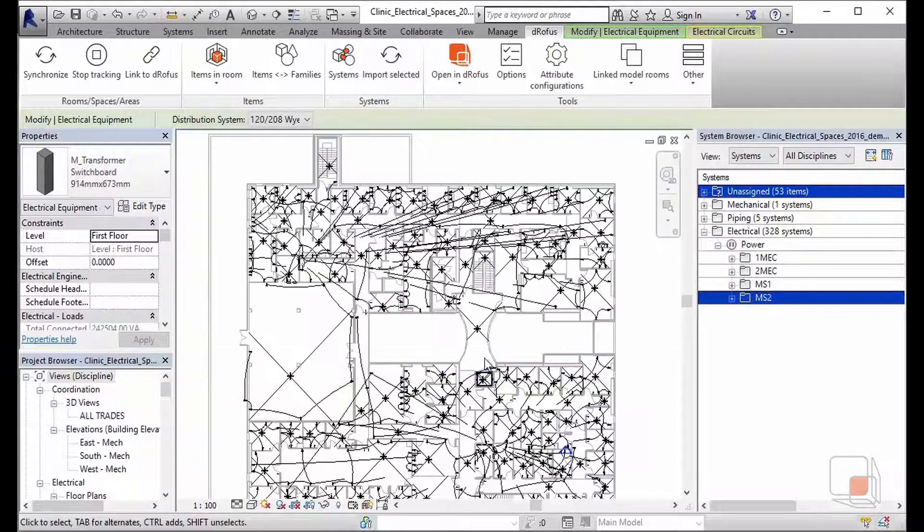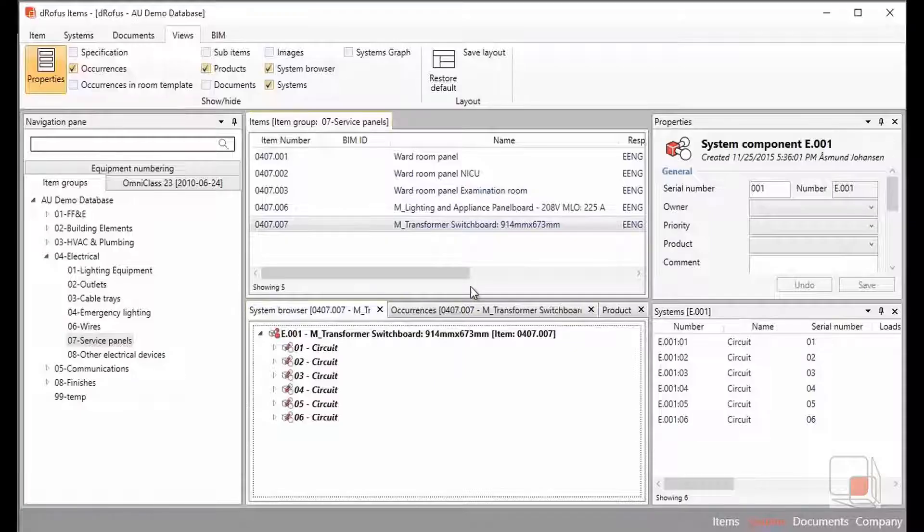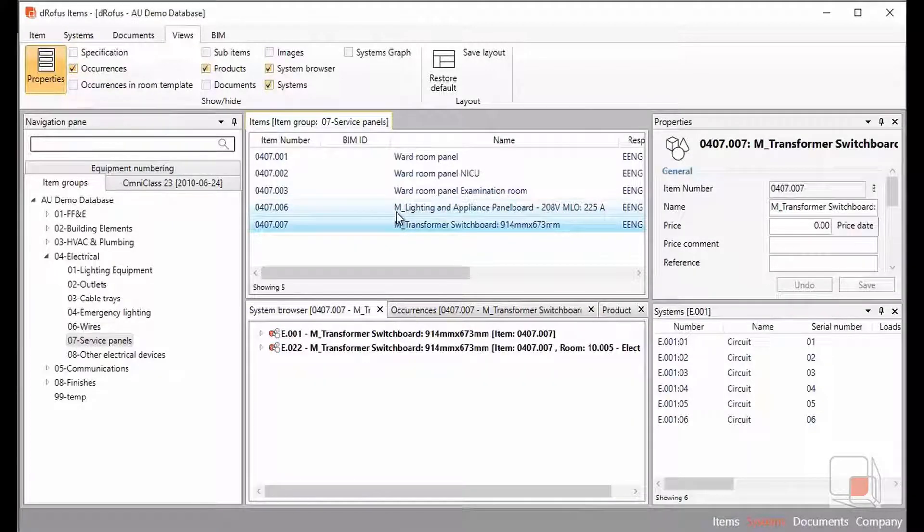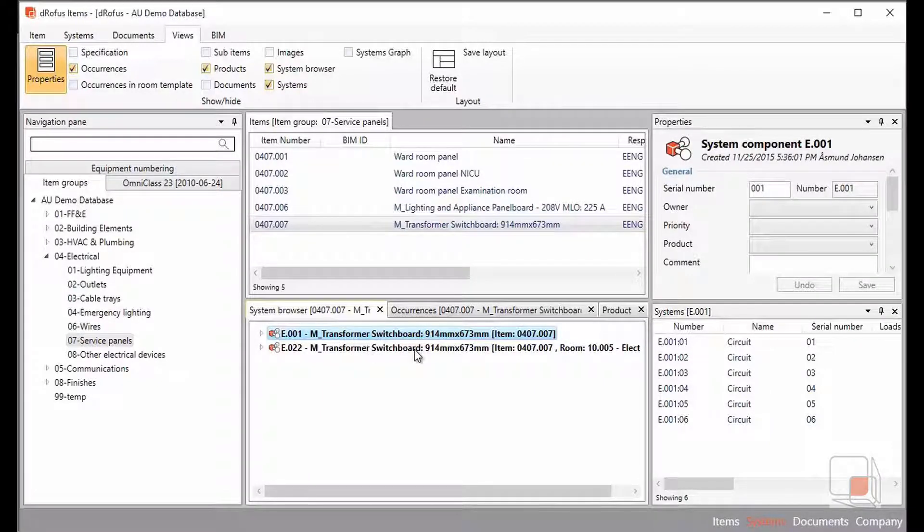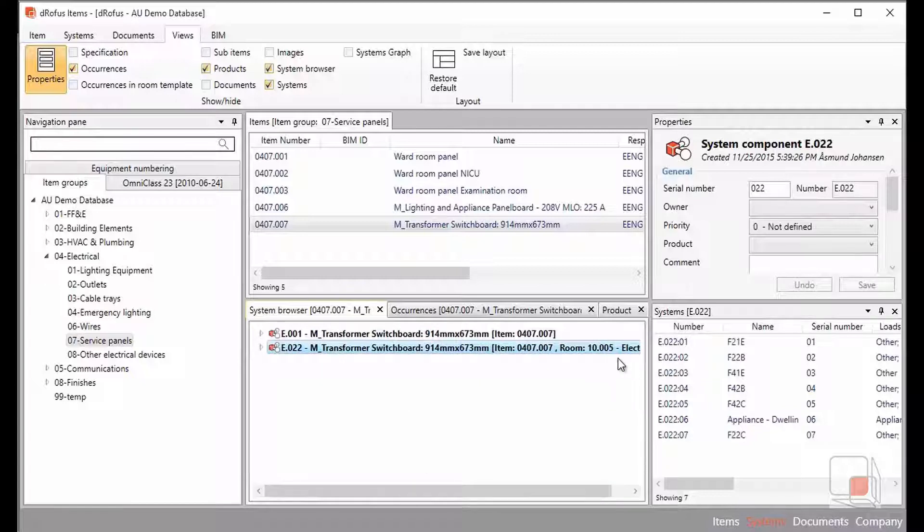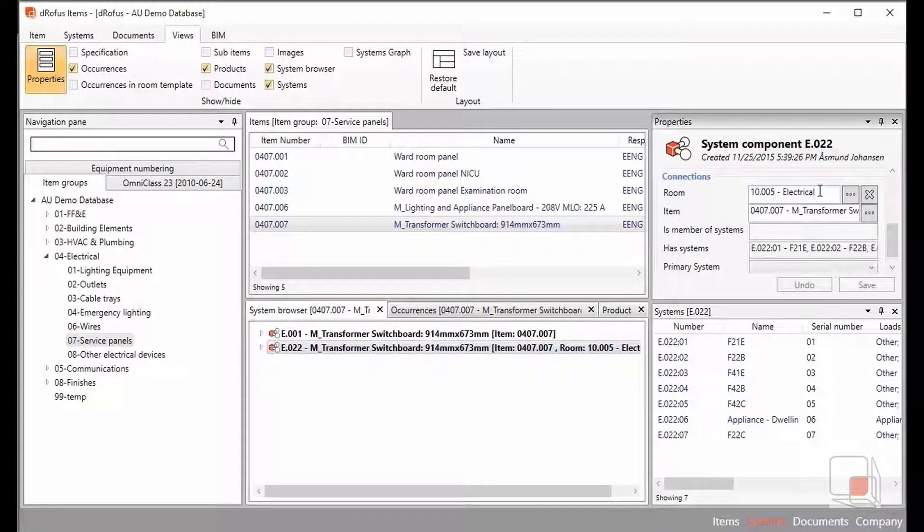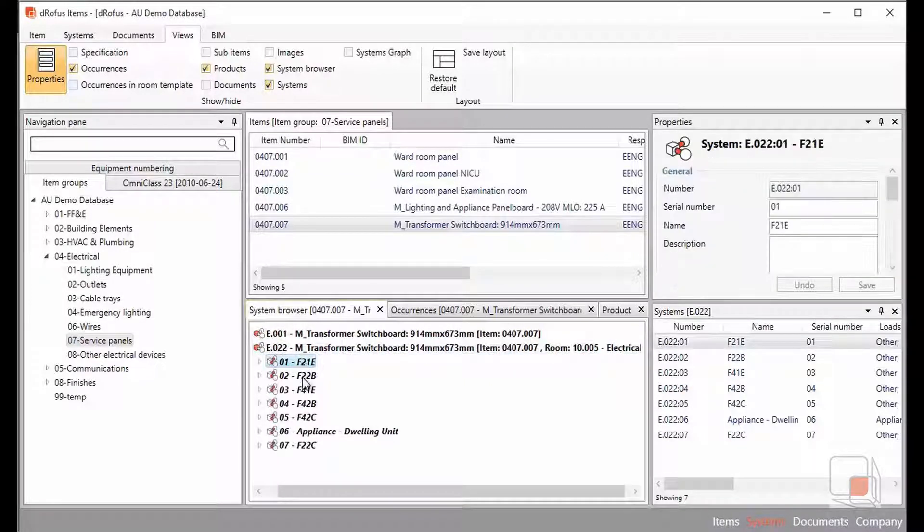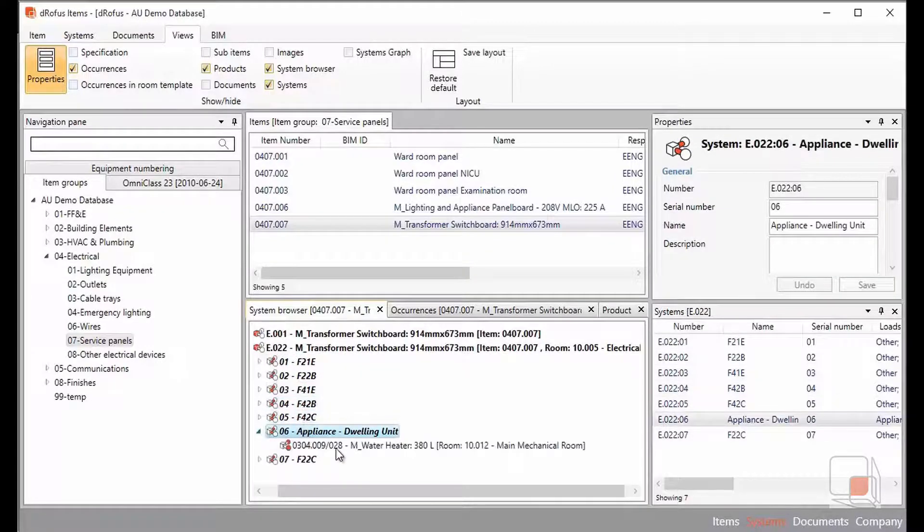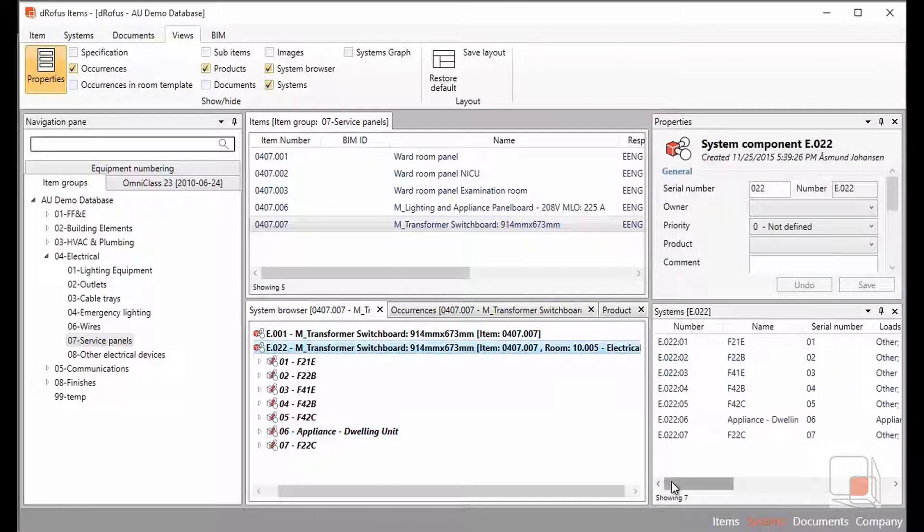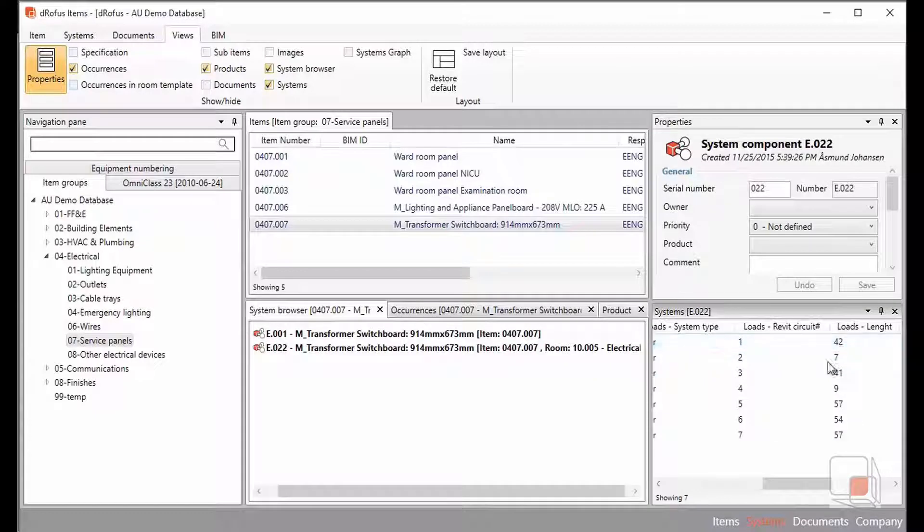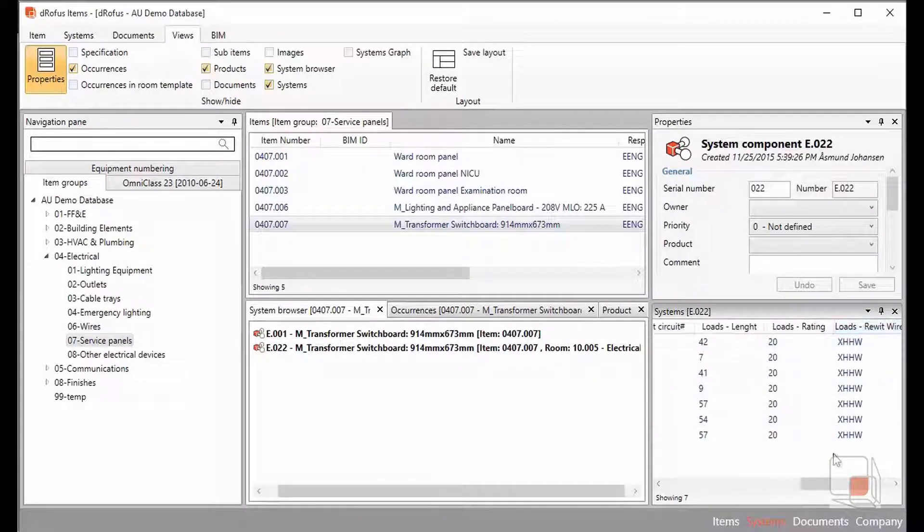Now if we toggle back to dRofus and simply refresh the view that we're looking in, now that transformer panel shows us two occurrences. The first one that I designed earlier from a planning exercise and the second one that's been imported directly from Revit. You'll see that there's even an association to which room that particular switchboard is connected to, down to each one of the circuits that it's connected to and then those components that are being supplied. We can see that the appliance dwelling was connected to my overall switchboard. You'll also see that all of the parameters that are associated to that component have been brought in as well.